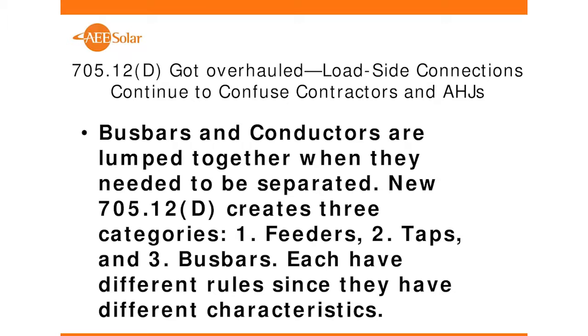So basically, in the past, really unintentionally, bus bars and conductors were listed in the same sentence. And we really didn't mean that as far as everything applying to everything, but because of that, there has been some very messed up views on how to size bus bars and conductors, particularly conductors. So what we did is we separated into feeders, taps, and bus bars. Each have different rules since they have different characteristics. And so we need to have them separate.